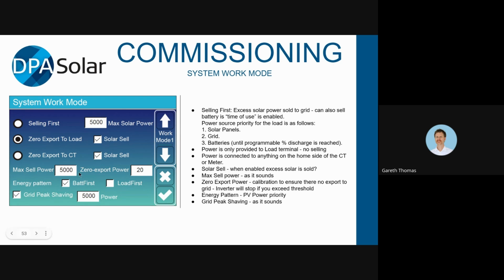The max sell power, well, that's as it sounds, that's just the maximum that it will ever actually sell to the grid. Zero export power is a calibration to ensure there's no export to the grid. So you might set that to 20 or something like that. And the reason for doing that is that if you want it to be 100% zero export, when you're on zero export, it will actually stop the inverter if you start feeding into the grid. So you can have this little offset value here, which is zero export, but pulling in a little bit to give you a little bit of buffer so you don't accidentally go over and get charged by your DNSP.